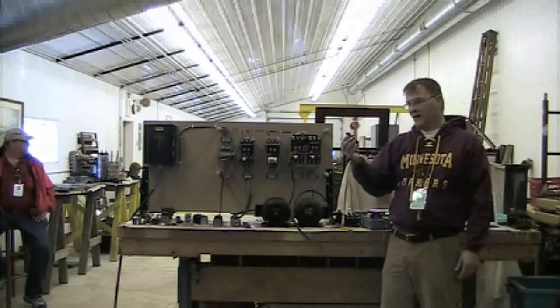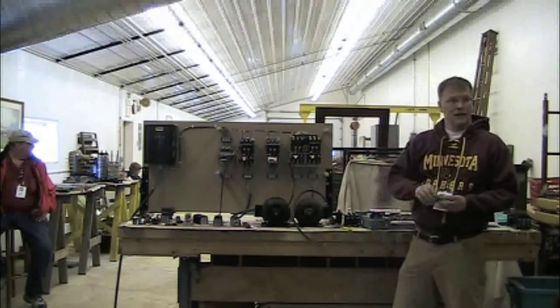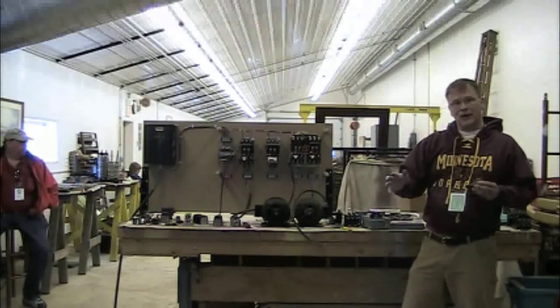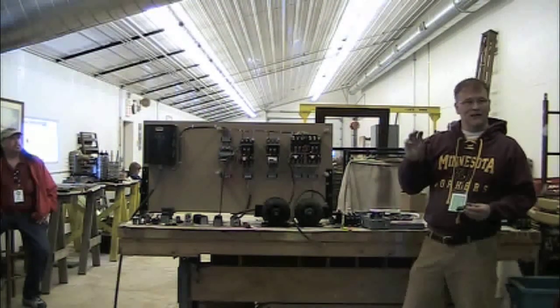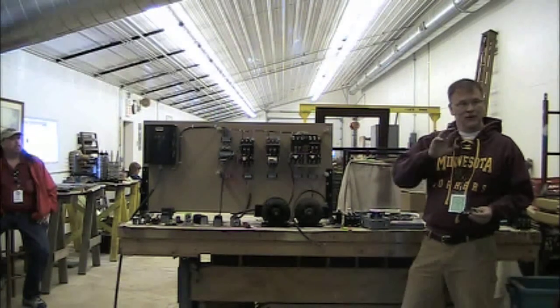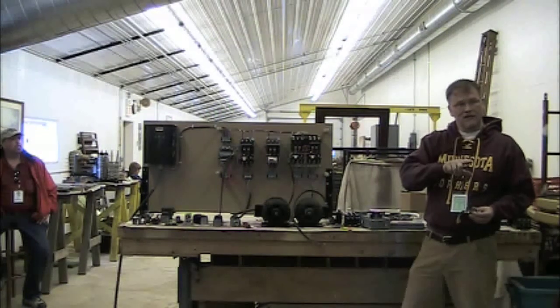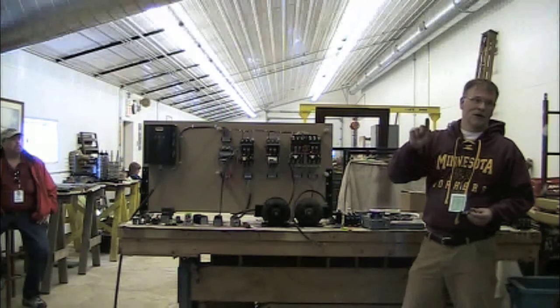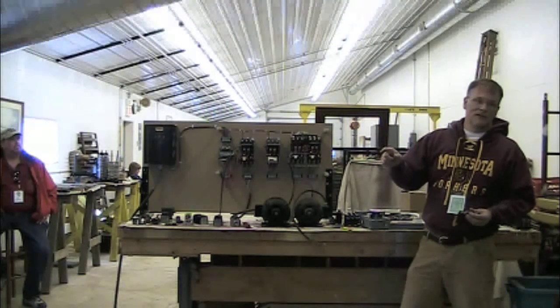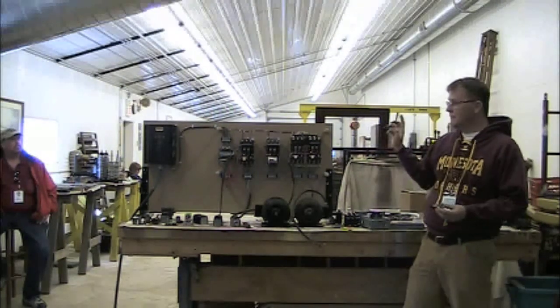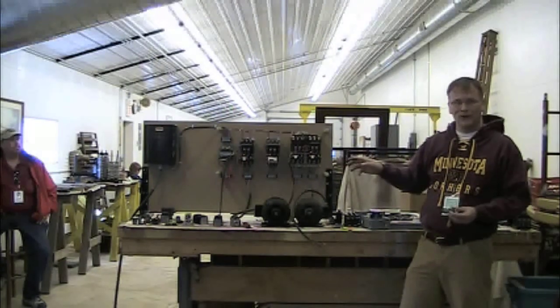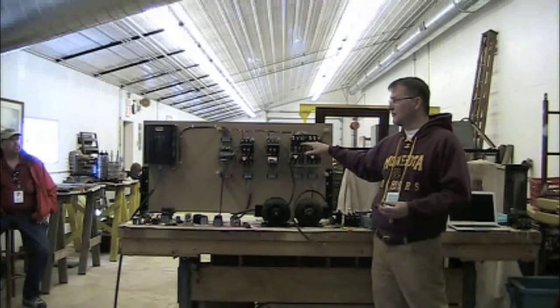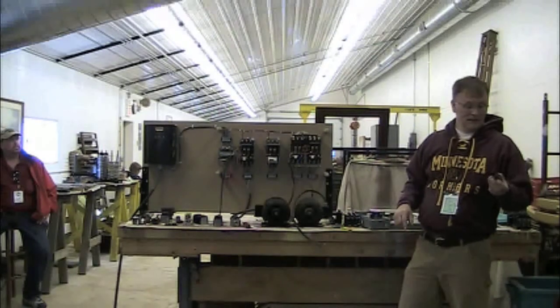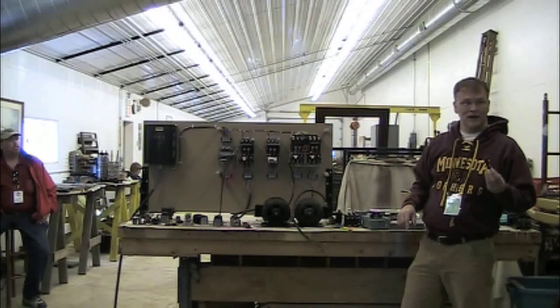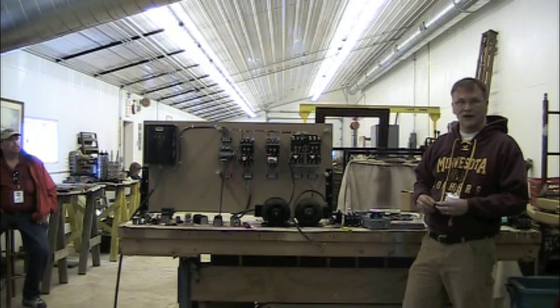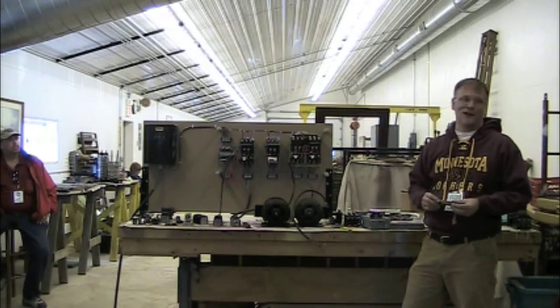When I built my phase converter, it's got an input contactor and an output contactor. It also has timers and stuff, so it sequences between firing the input contactor and starting the motor. It has a delay, and then it fires the output. It's all done with just industrial relays, and it required a few extra of these little contact blocks on the main starters. They're easy to find if you know what parts you're looking for.